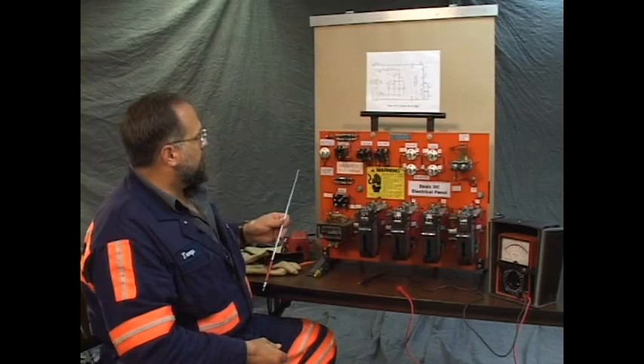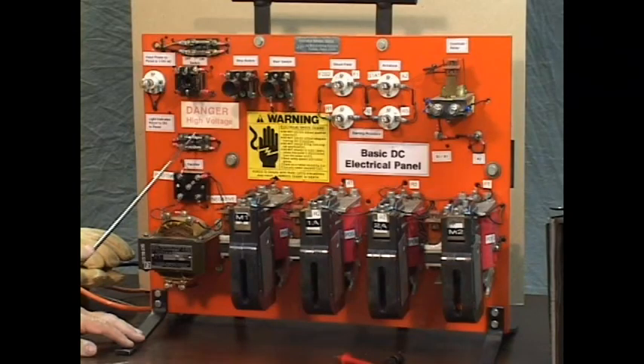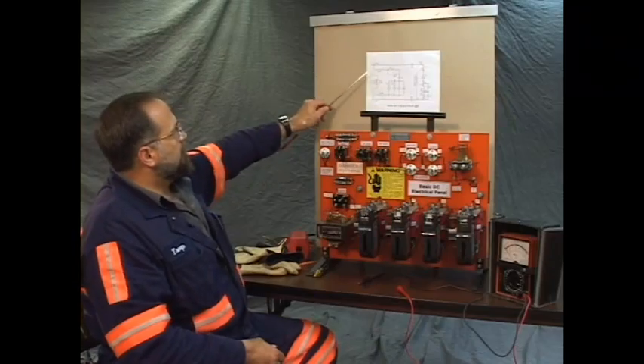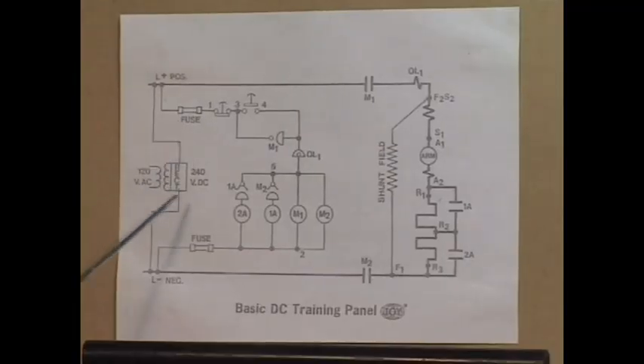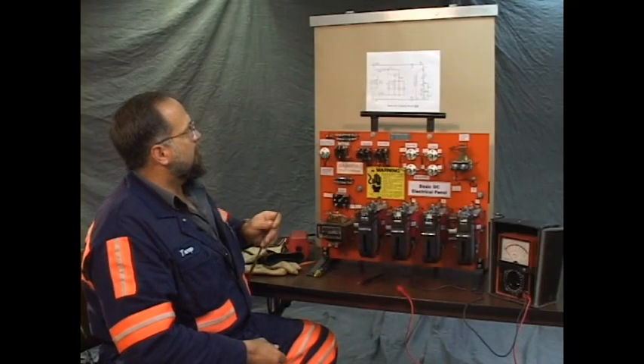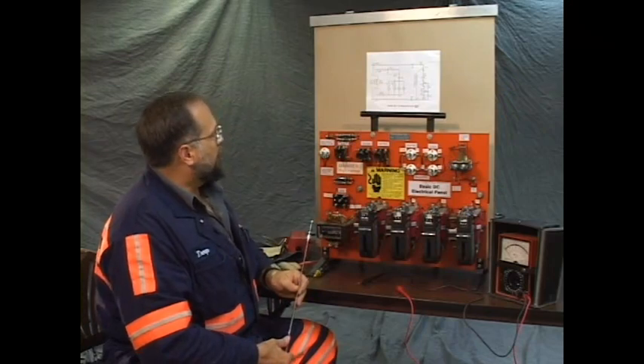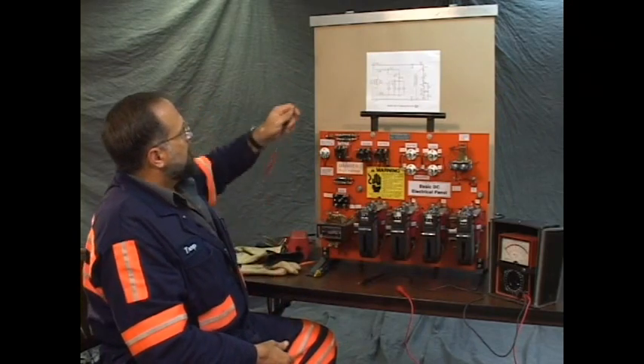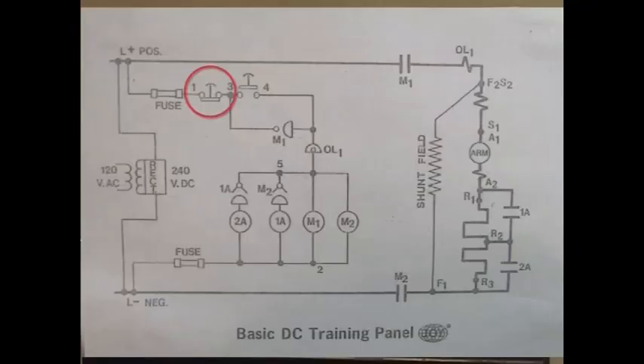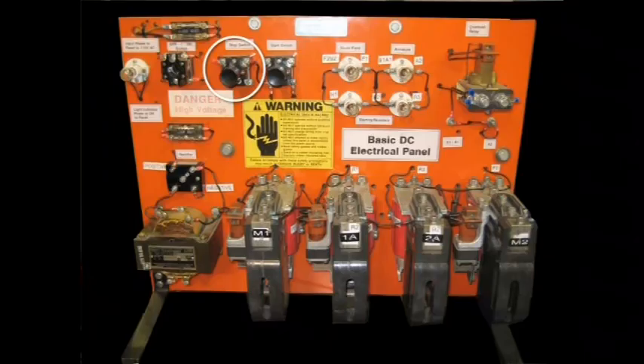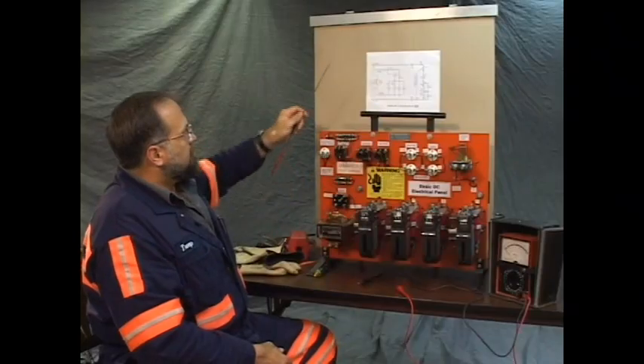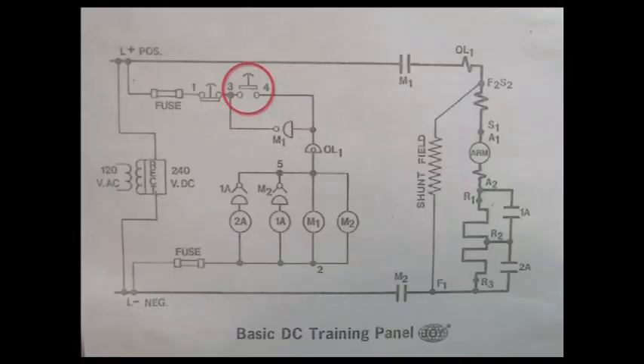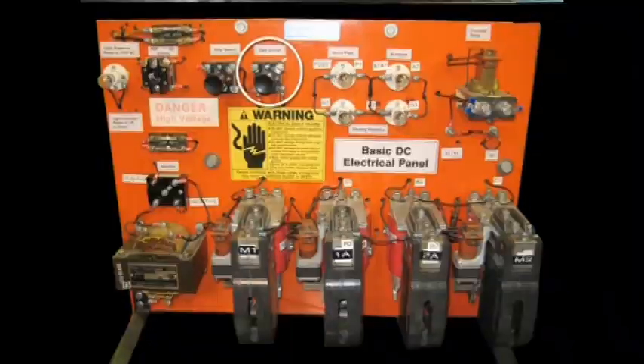From there we go to fuses. There's a positive fuse and a negative fuse. On the print, positive fuse and negative fuse. We have a stop switch. It's a normally closed momentary switch, push button. That's here. We have a start switch, normally open, momentary switch. That's here.